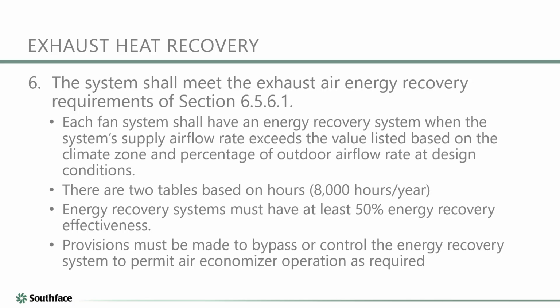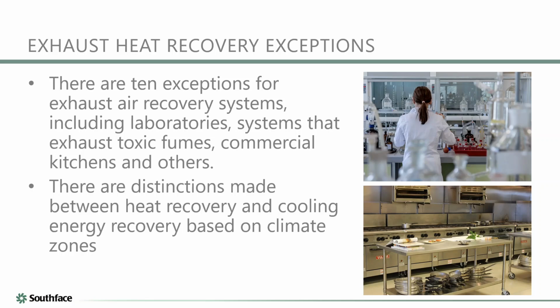And of course, as with most things in the code, there are different exceptions. We see this one come up a lot when it comes to labs or healthcare facilities, which end up being exempt from some of these requirements. Also exempt is anything exhausting toxic fumes, or commercial equipment. You're probably not going to be able to extract much cooling energy out of a kitchen range hood, because it's going to be pretty warm. Keep in mind that there are distinctions made between just heat recovery and cooling energy recovery, and that's based on climate zone. And we do have how many counties in Georgia? Six or seven counties that are in climate zone 4, which they consider a cold climate. So that would be a slightly different lookup for climate zone 4.